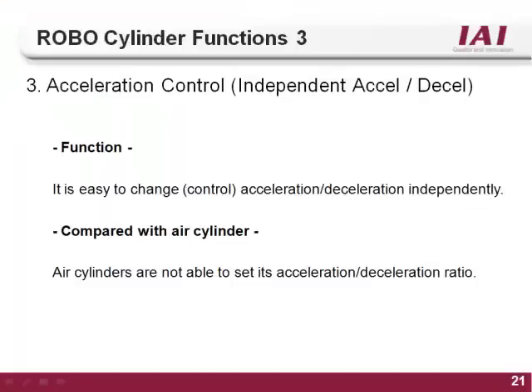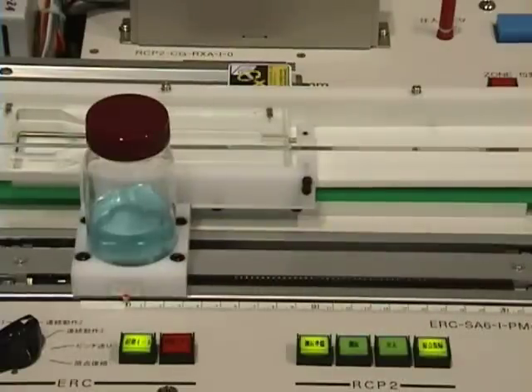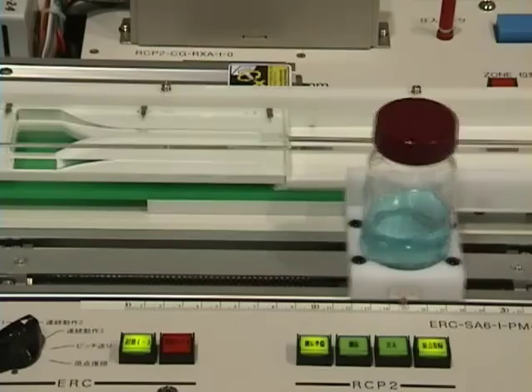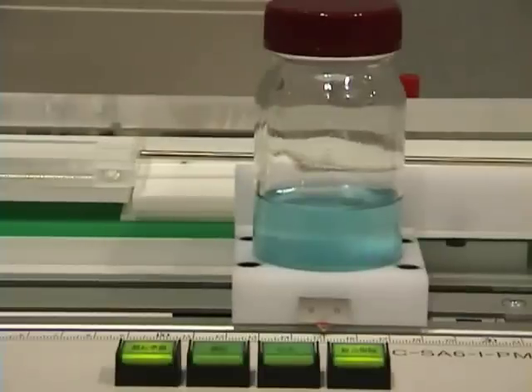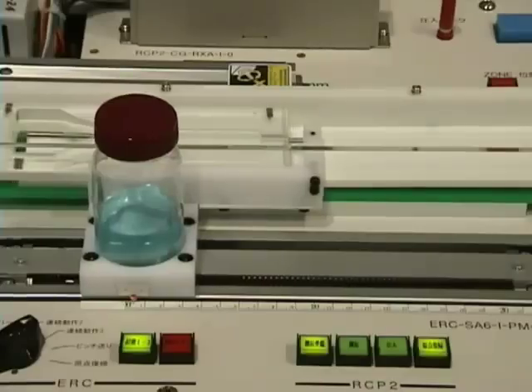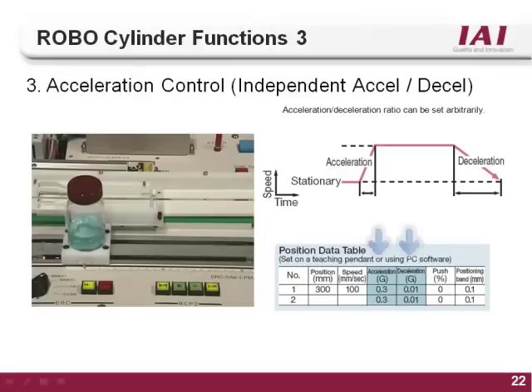The third function of the RoboCylinder controller is acceleration control. On an air cylinder, the speed is determined by the line pressure and flow control valves and cannot be changed for different positions. Because of this, air cylinders will slam into the end of stroke, causing part defects or damaging the actuator itself. With the RoboCylinder controller, you can set the acceleration and deceleration for every move. This allows you to have smooth start and stop motion, which causes fewer defects, gives individual control for every position, and allows for longer actuator life. The acceleration and deceleration is set inside the position table, with a separate column for each, so you can have a different ramp up speed than your ramp down speed.